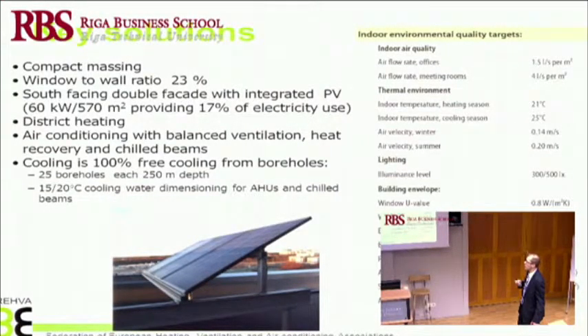The building uses district heating, which is very typical in Finland and other Nordic countries, also here in Latvia. It has air conditioning and balanced ventilation with heat recovery, but all the cooling for the air conditioning comes from the boreholes - there are no chillers in that building.